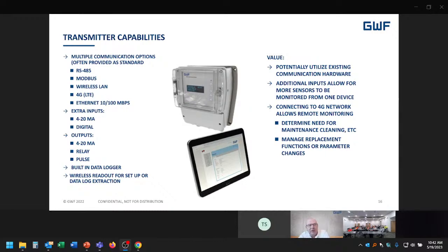They also can take in extra inputs. So a lot of systems will take in extra 4 to 20 milliamps or digital devices. What's the benefit of this? Well, if you're able to start monitoring additional 4 to 20 milliamp sensors, you could be putting in a temperature sensor in a manhole, and if you see a drop in temperature, you could well be looking at an inflow or infiltration issue. Or you could be monitoring pH or other factors to be able to see if there's a problem or change during normal operation. Outputs, again, you could potentially be providing multiple 4 to 20 milliamp outputs for SCADA, maybe relay output for being able to turn on and off an actuator, or even pulse into another system.